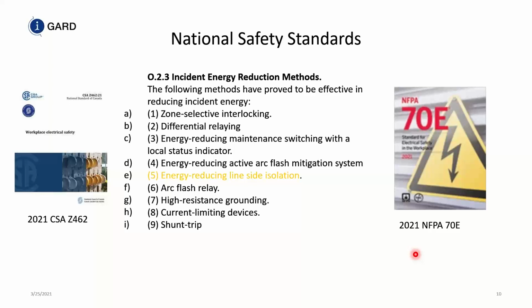All of these protective measures, other than number 7 or G, reduce incident energy, but they only come into effect after the fault has occurred. So they reduce the time that the fault is on the system. And when you reduce the time that the fault is on the system, you reduce incident energy. Because according to IEEE 1584, incident energy is directly proportional to time. If you can cut your clearing time in half, you reduce the incident energy by a factor of 2.